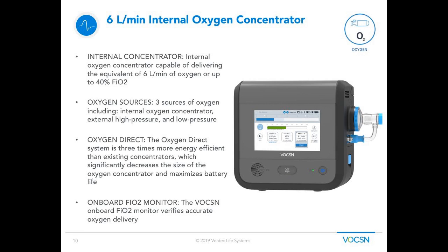VOCSN has the internal concentrator that's actually going to replace a stationary or portable oxygen concentrator, tanks, or wall oxygen. And it's going to deliver that oxygen through what we call our oxygen direct system. So if you see in that photo there on the right, you see the image of the oxygen tube coming out of VOCSN - it's actually going into the circuit, and that tube is inside the circuit, delivering the oxygen proximal to the patient, right at the patient connection to the circuit, delivering the oxygen in the first two-thirds of the breath. So when the patient needs it the most, on the front end of the breath, our oxygen direct system is delivering the oxygen.